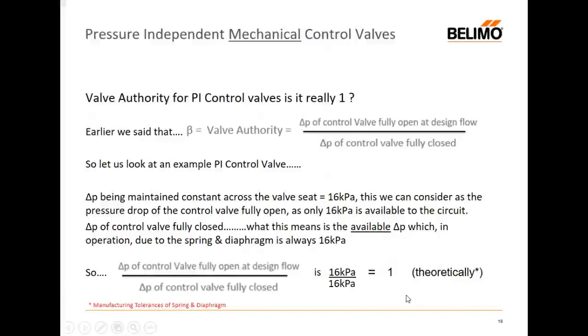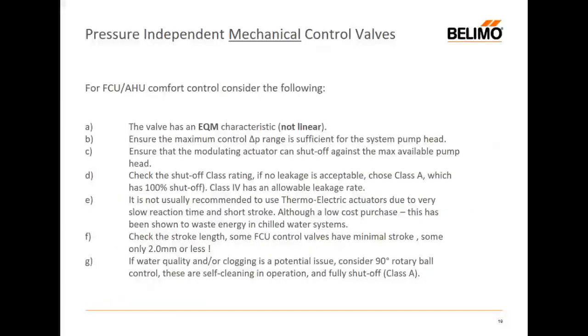It's certainly better than 0.5. It's certainly better because it's dynamic, and it's certainly a lot less likely to be eroded because the spring and the diaphragm are maintaining constant the available pressure, even though we're in a variable flow, variable pressure system. On the circuit that's being controlled, we're maintaining a constant pressure. So in that sense, we have a valve authority very, very close to 1.